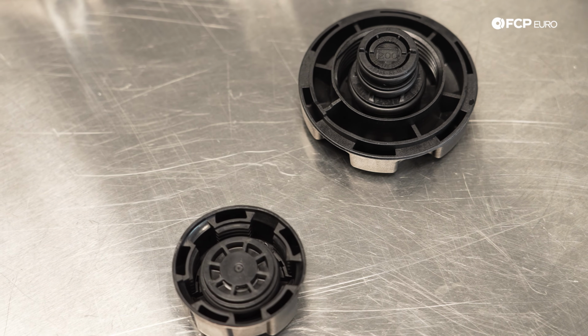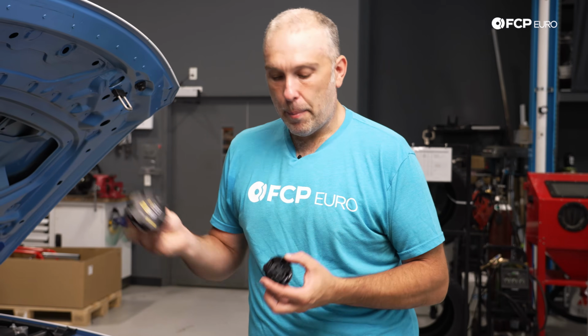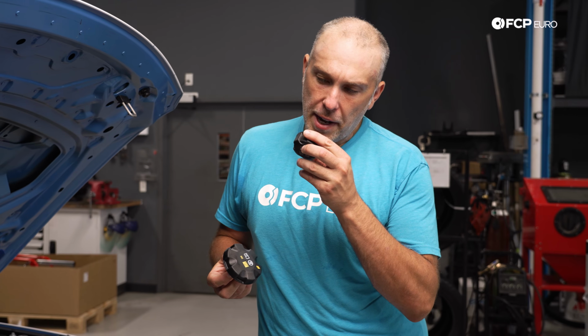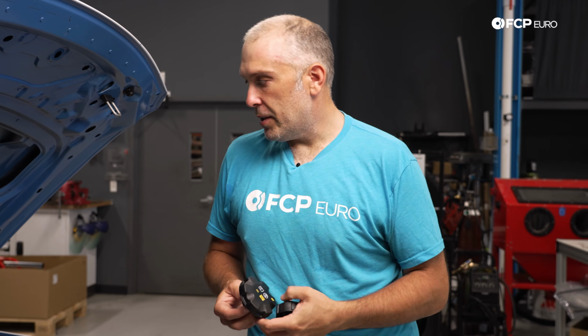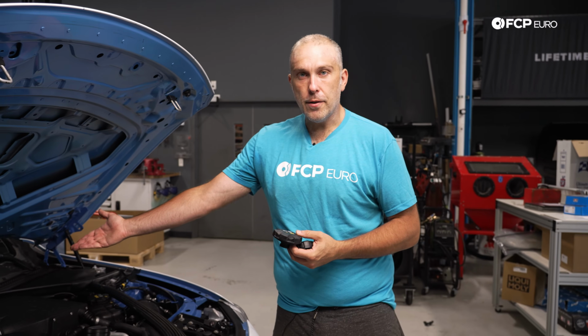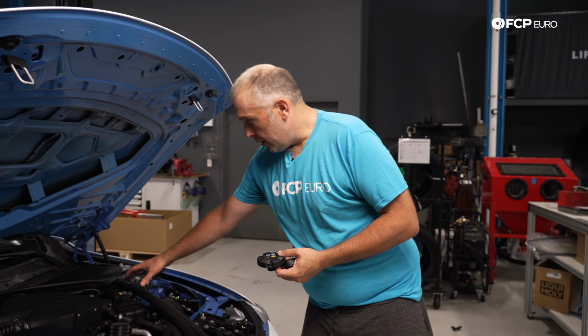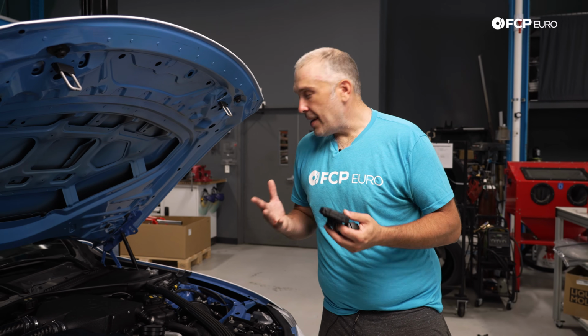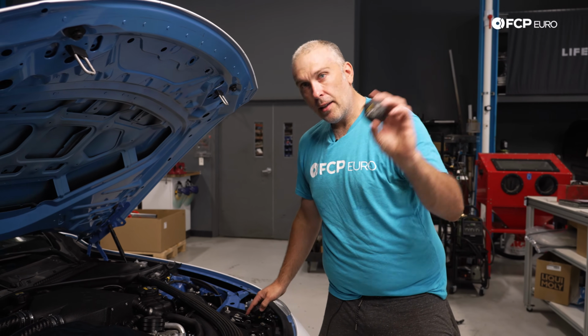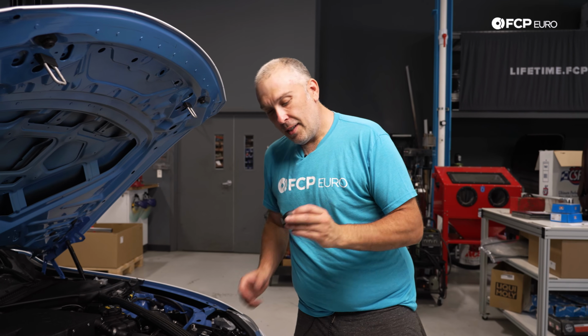These caps are pressure regulating, so for example, this is a 2-bar cap. I wish I knew what the rating was for the smaller cap, but what's interesting is there's not going to be a lot of pressure in that low temp circuit. There's going to be a lot more pressure in the high temp circuit, strictly because of volume. That said, I'm going to show you something about the low temp circuit expansion tank cap.